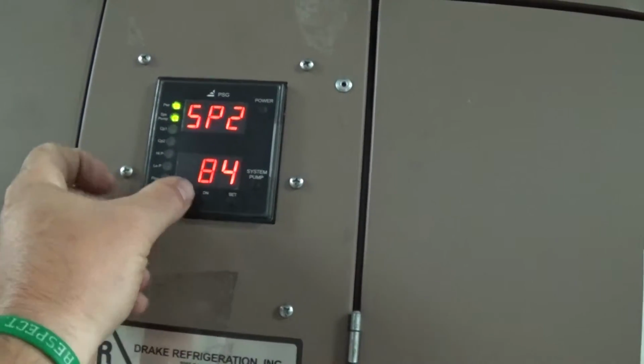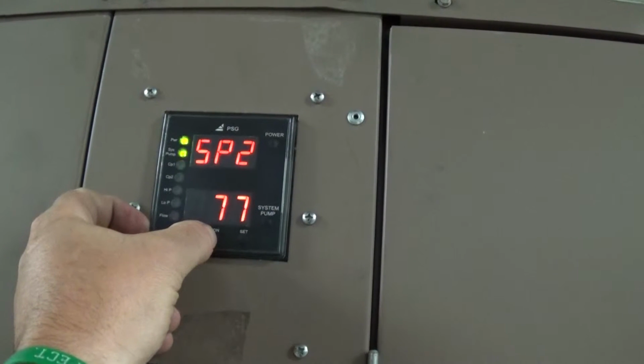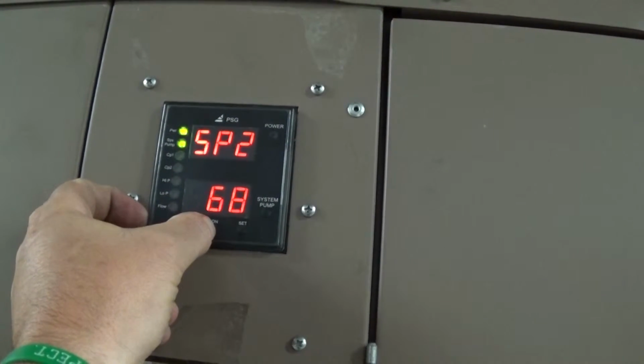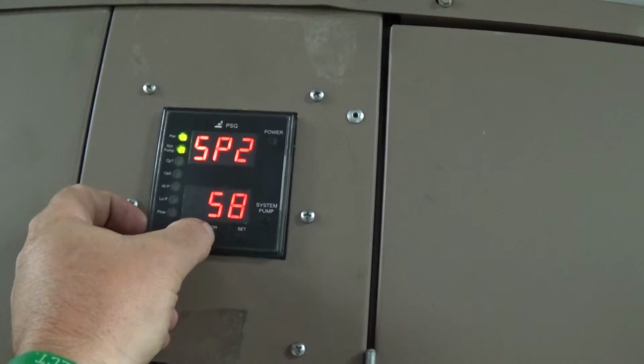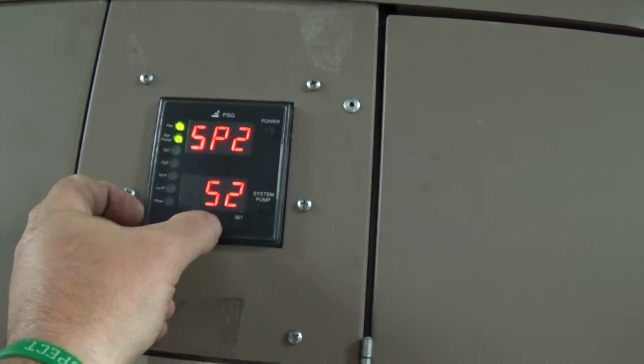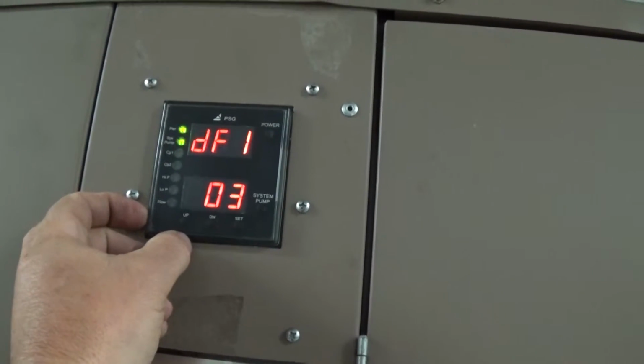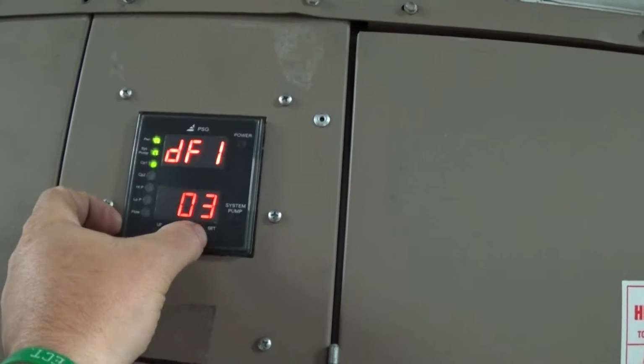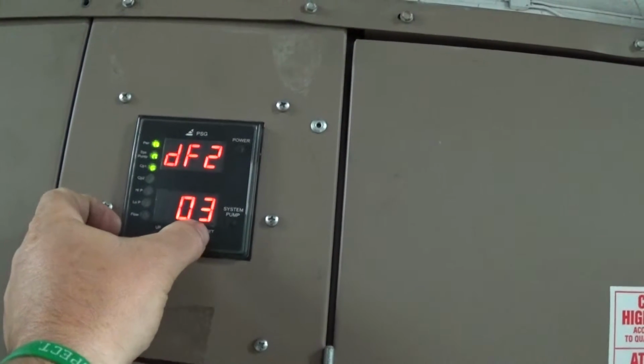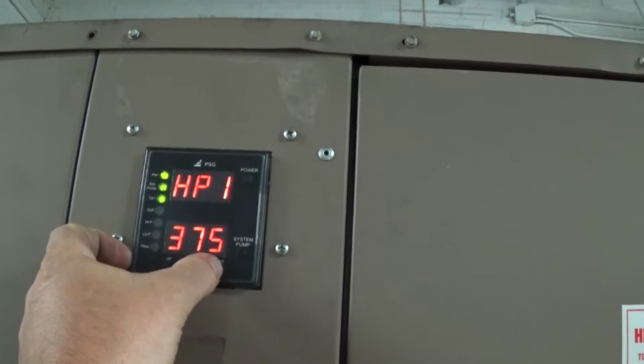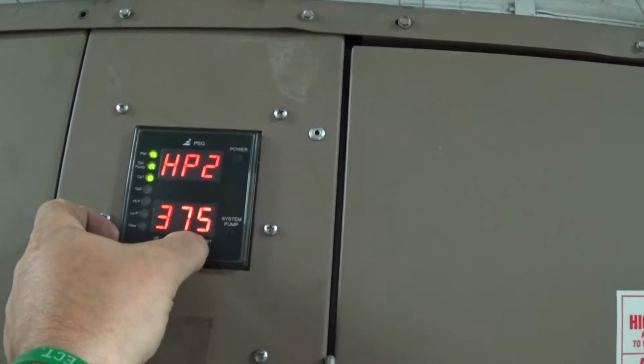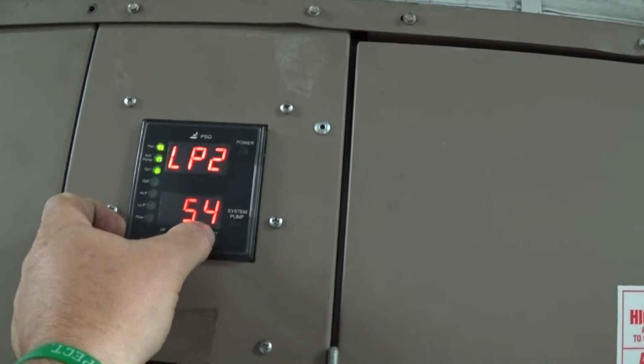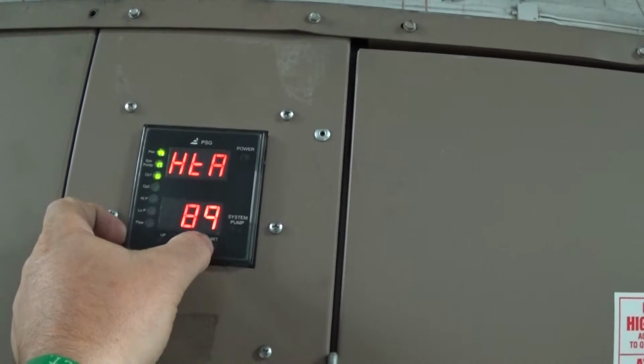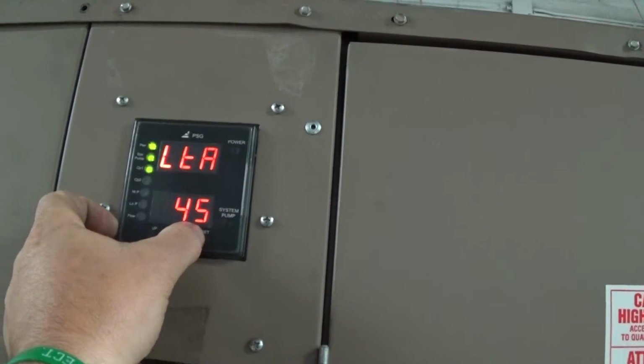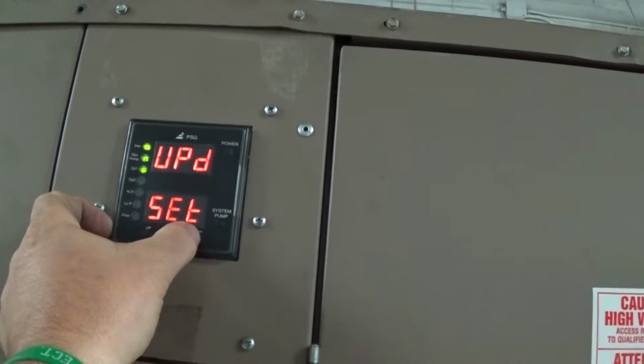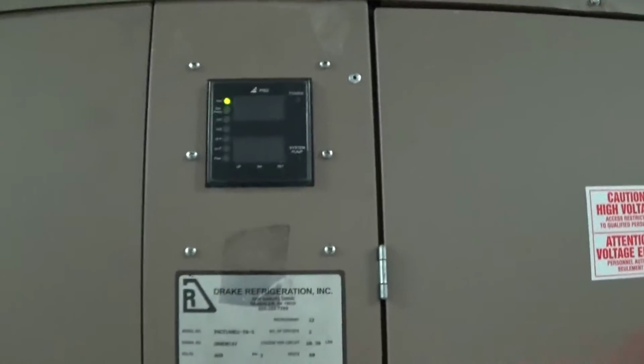I'm going to press set compressor 2, or set point 2, at 52. In the real world, you might want to have them both at the same temperature and just the differential different. And I'll show in a second. So this one's at 52. Differential for 1, let's leave it at 3 degrees. Differential for 2, leave it at 3 degrees. Then set again. That's your high pressure 2, low pressure 2 for refrigerant. High temperature alarm at 89, low temperature alarm at 45. Update, then you have to press set for those to be saved in there, okay?